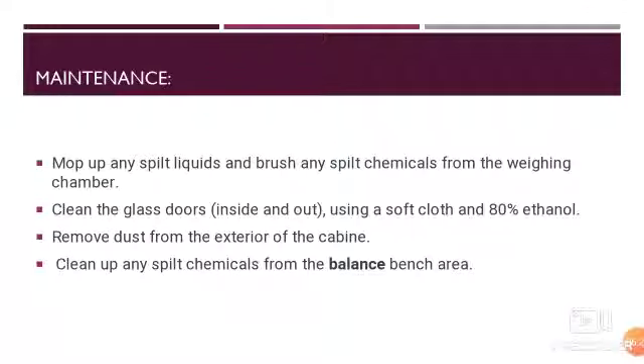Number one: mop up spilled liquids and brush any split chemicals from the weighing chamber, then clean the glass doors. Remove dust from the exterior of the cabinet and clean up any spilled chemicals from the balance bench area. If there is a chemical or sample left in the analytical balance, you must clean it so that the next time you measure a sample, the previously spilled material does not affect the weight reading. Before taking measurements of any sample, clean the analytical balance, and after you are done, clean it with a soft cloth.